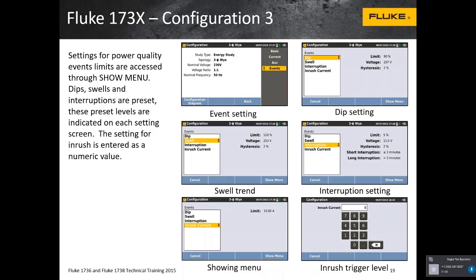When you're using energy study, it's going to capture that information and store it for you with detail, as well as inrush current, and you can set inrush triggering too. So if you're trying to determine if there's a systematic event, a lot of times they're very intermittent, and these tools will detect down to half a cycle time of change.